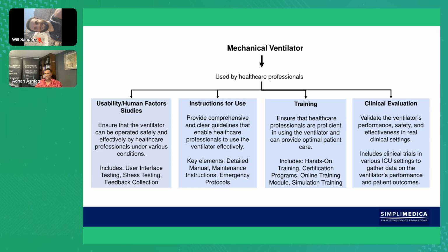Within the clinical evaluation, we'll look at the possibility of clinical trials. What are the claims that we're making? Are they based on predicate devices? Are these devices that have already been in the market and used for X number of years? And there's so much data and published literature that we can utilize the published literature, and we don't have to do the clinical trials, because nobody wants to do clinical trials. Of course, face it, clinical trials are a very expensive, long, and cumbersome process. So we want to see if there are any other predicate devices.